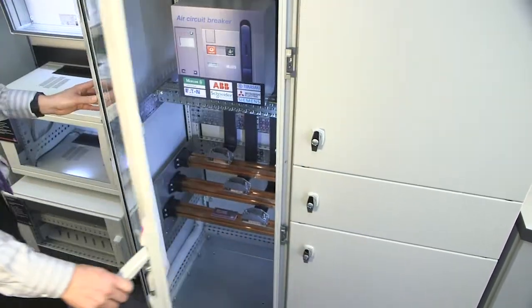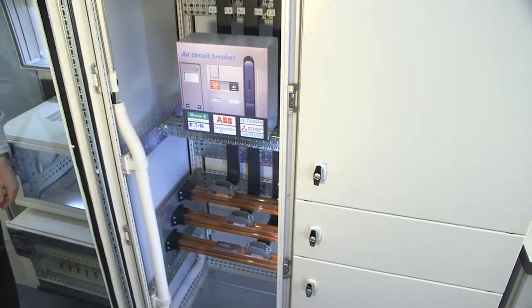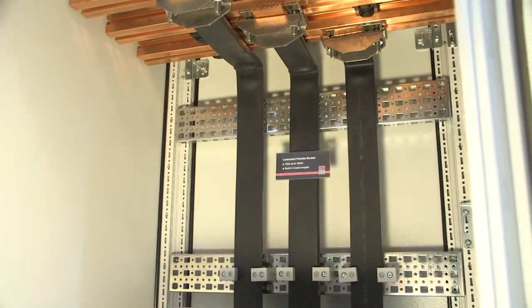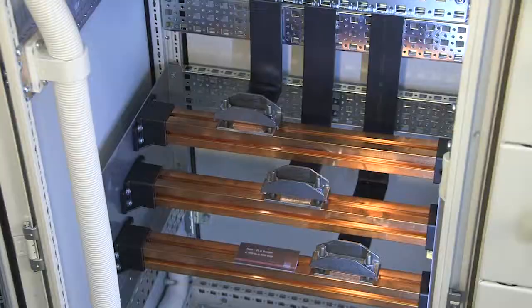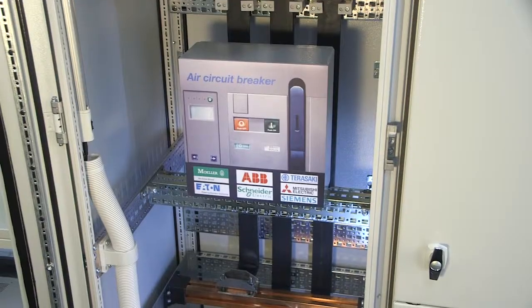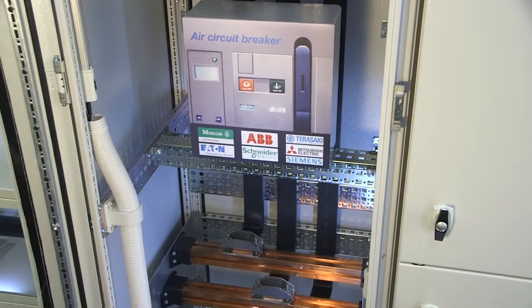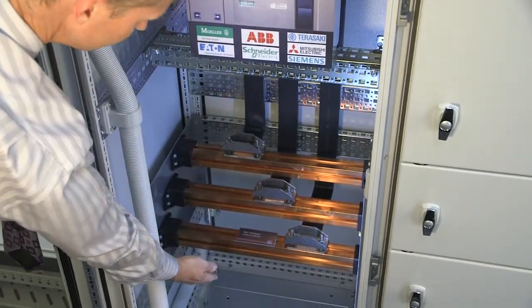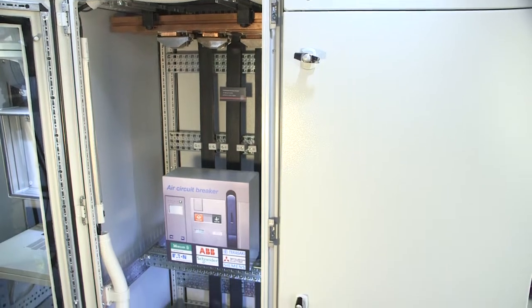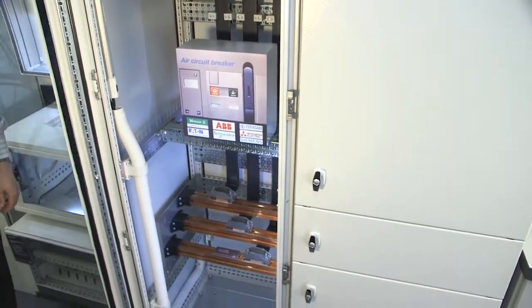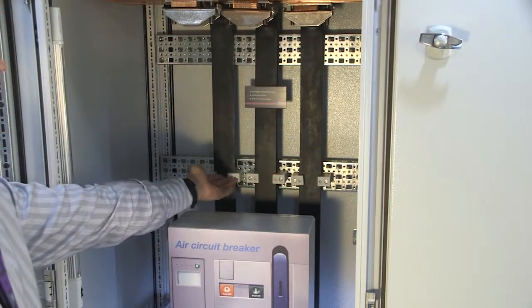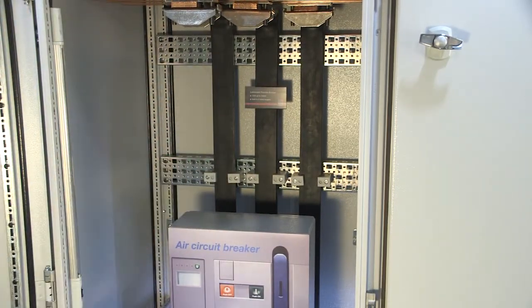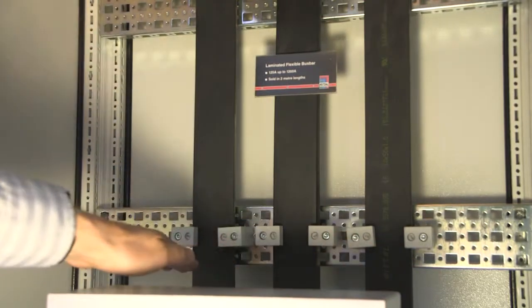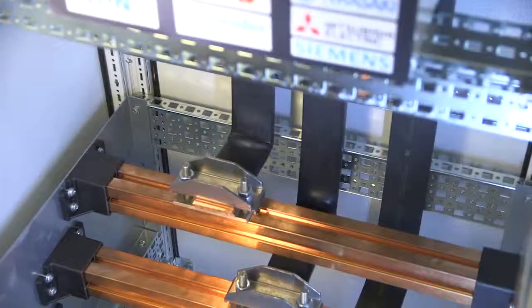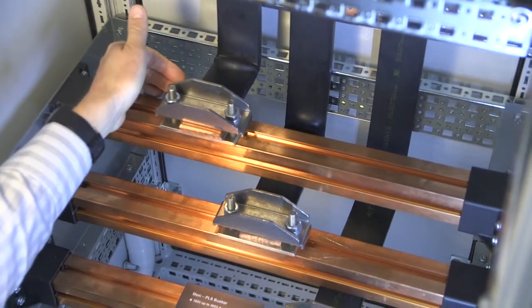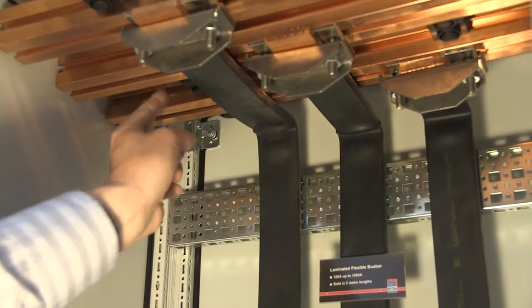The adjacent enclosure includes the main power distribution installation with Rittal-shaped profile Maxi PLS busbars at both the top and the lower part of the rack, permitting the main feed at the top going first to the breakers and from there to the components. This can be configured to handle up to 3,200 amps while meeting CSA and UL certifications. Another notable feature here is the use of laminated flexible busbars. Sold in 2-meter lengths with up to 1,200 amp capacity, they save substantial interior space by permitting 90-degree bends to maintain a grid pattern within the enclosure.